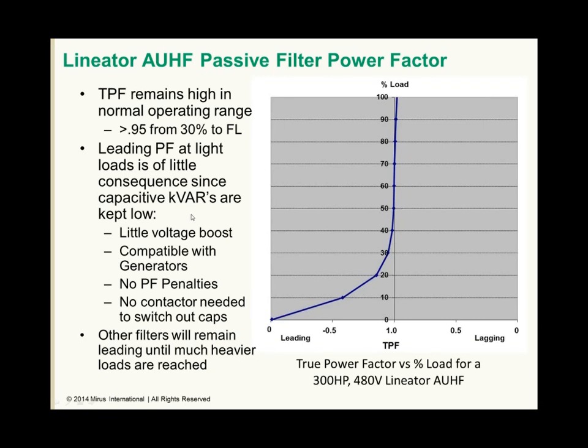The leading power factor at light loads is of little consequence since capacitive reactance in kVARs is kept low. There's little voltage boost. We're compatible with the generators. We will not introduce power factor penalties because this is only at light loads, and no contactors are required to switch out the capacitors. Again, as I mentioned earlier, other filters will remain leading until much heavier loads are reached and therefore will require cap switching contactors.